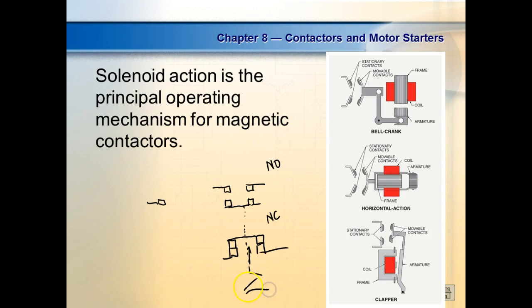Contacts like this, we refer to as normally open. Contacts like this, we refer to as normally closed. They could be connected to exactly the same operator. So my solenoid down here, when it generates that force, it would come up here and open this contact and close that contact. So in motor controls, that's the symbol we give a normally open contact, and for a normally closed contact, we use this symbol right here.